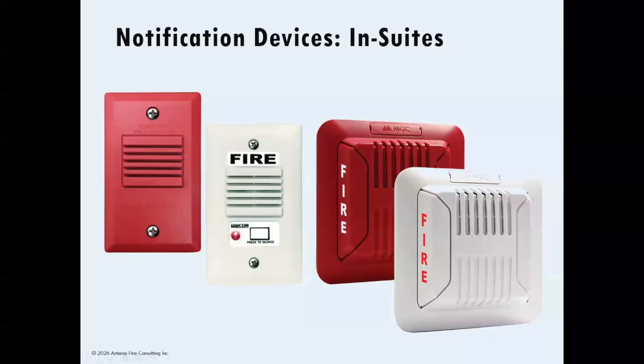Mini horns, the little devices on the left-hand side there, have been used for many years to achieve the code requirements of both the decibel level and the requirement to give homeowners the ability to silence the mini horns in their suites. You'll see that the white one here has a little button that you can push to silence the horns. With the increasing computerization of fire alarm panels, many of these systems provide automatic signal silencing now directly from the panel, negating the need for that silence button in the suites. This has led to the use of horns on the right-hand side in suites, which can provide the low frequency sound instead of the smaller mini horns, which are very loud and quite high.